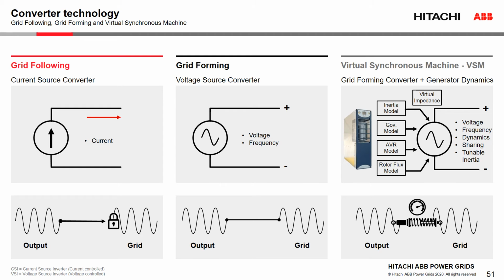This brings us to the right, virtual synchronous machines. Virtual synchronous machines are grid-forming converters plus the dynamic behavior of a synchronous machine. The comprehensiveness and detail of virtual synchronous machines vary by vendor and have different levels of complexity. Here is an example of a 5-part virtual synchronous machine model, which contains a virtual impedance, inertia model, governor model, AVR model, and rotor flux model. As the picture shows at the bottom, this acts like a shock absorber. It allows the grid-forming converter to operate in parallel with other voltage sources, if they are synchronous machines, or the grid.